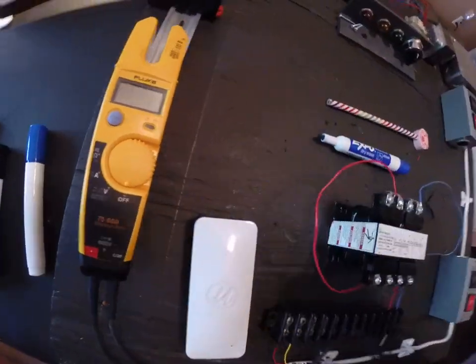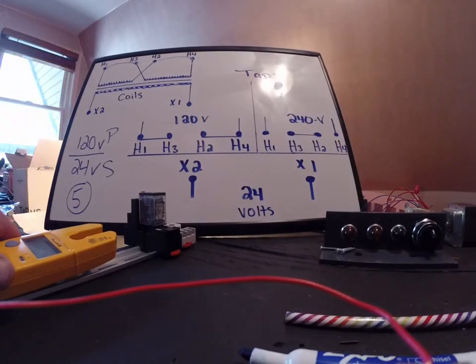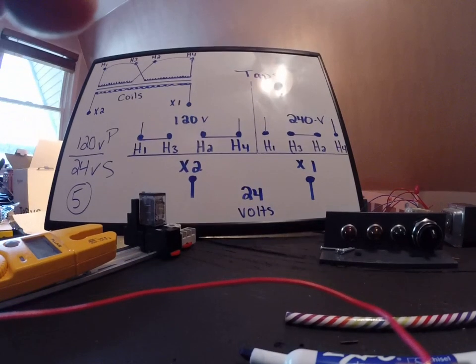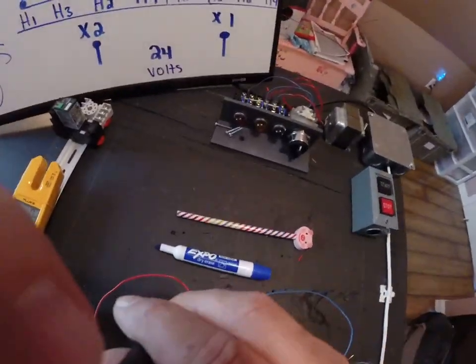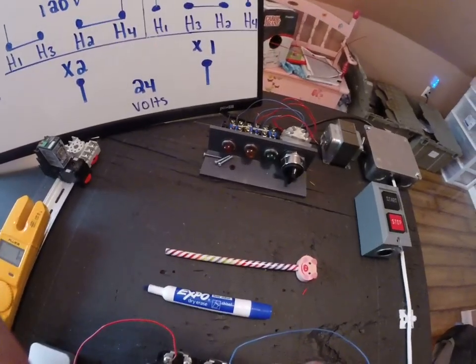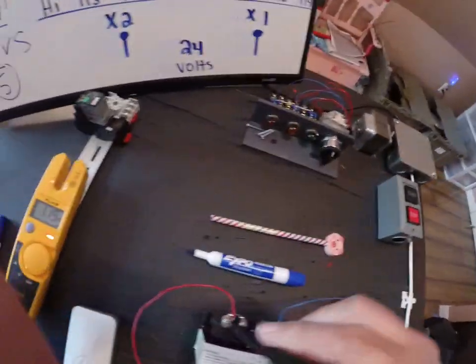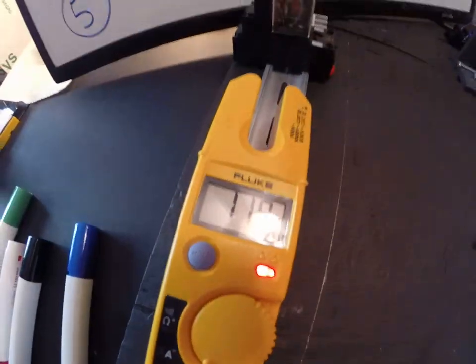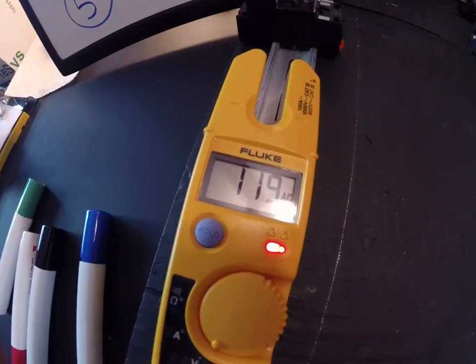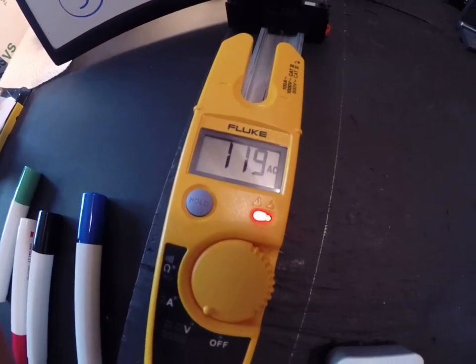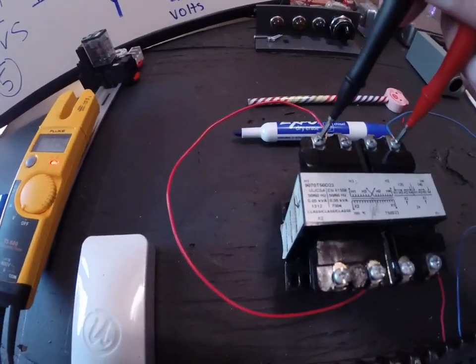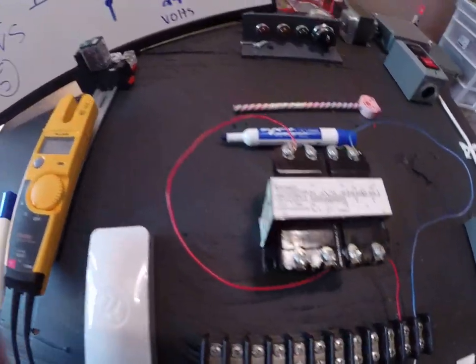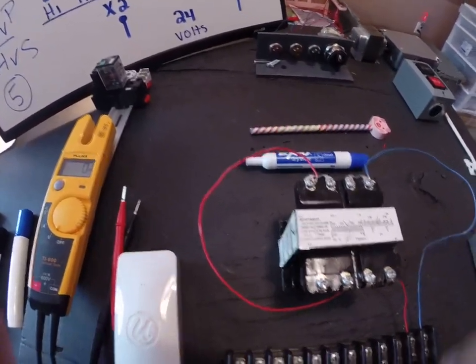If we wanted to verify that, we could simply just turn my meter on. We'll verify that I have 120 volts. I'll put my meter on here. My meter is across H1 and H4. And I've got 119 volts. Exactly what we want, give or take.